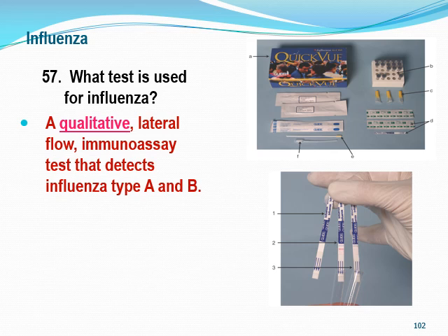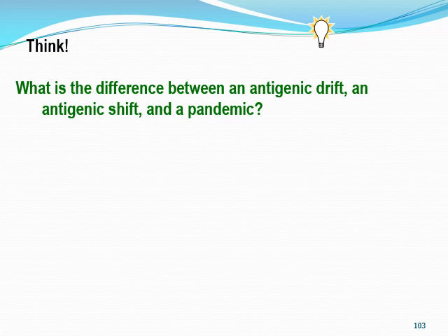and the importance of making sure your internal quality control works, making sure that you read the package inserts, and you should have a place in your lab, whether it's a big lab or a small lab, where you take that package insert and it is kept in a book so that you can go back and refer to that package insert each and every time. And again, always make sure you do not move items from one kit to another, and each and every time you get a new kit in, take that package insert out, go over it, place it in your book, and make sure that it's there for any new employees to be able to go back over that procedure.